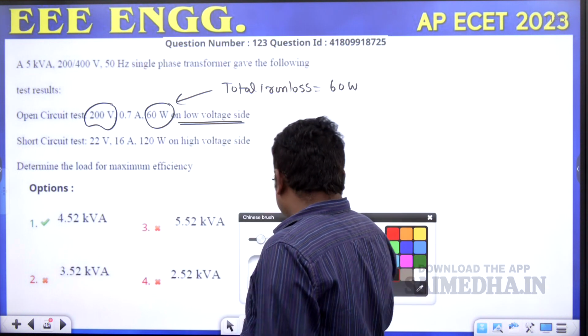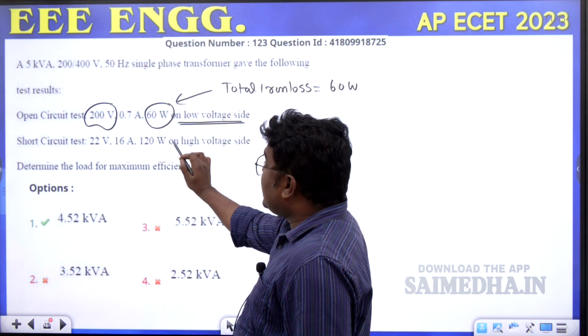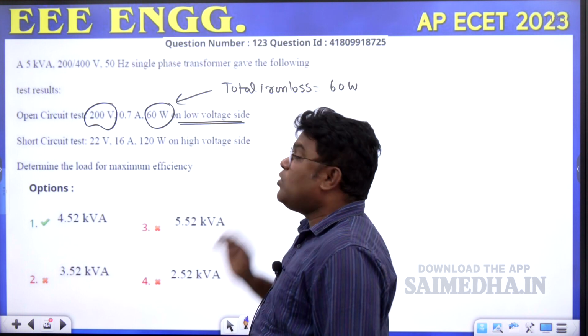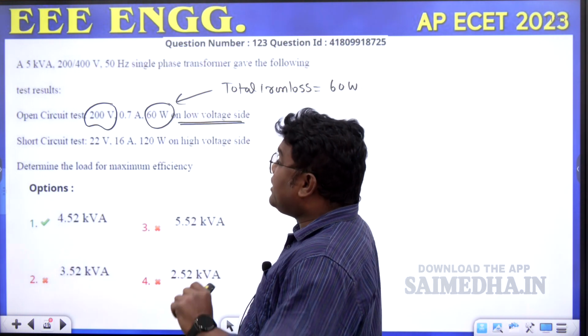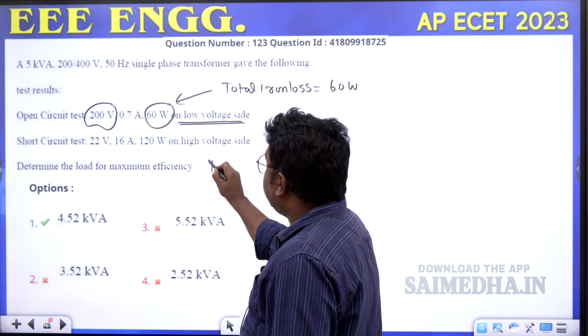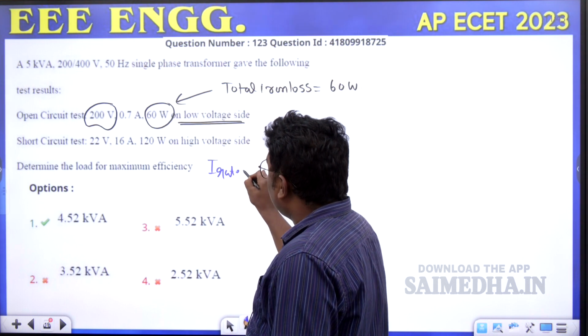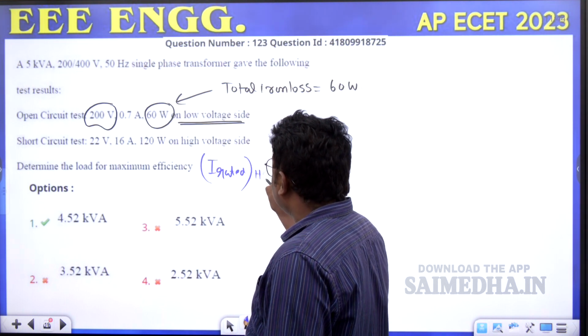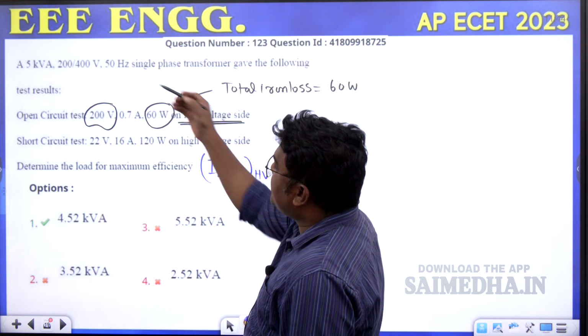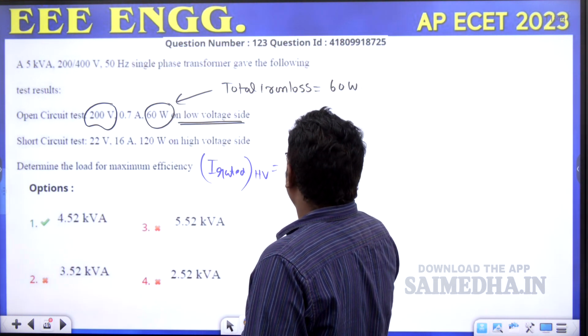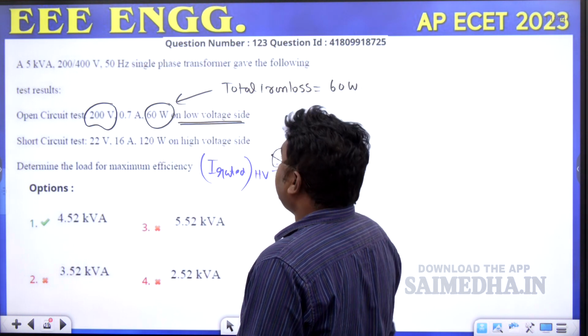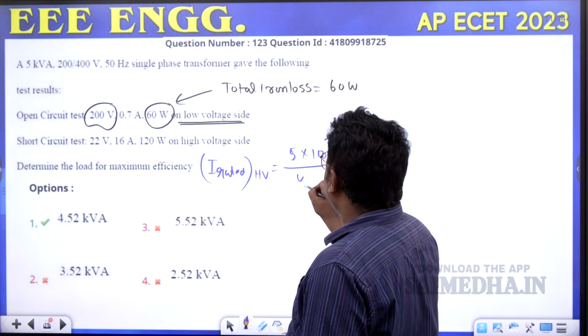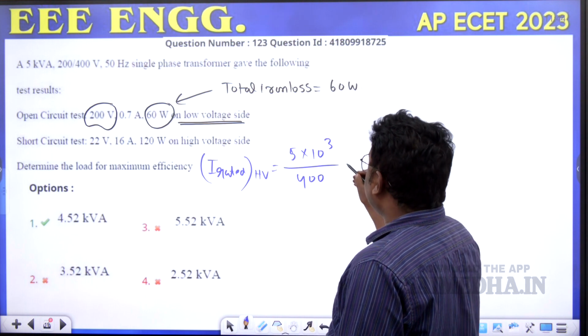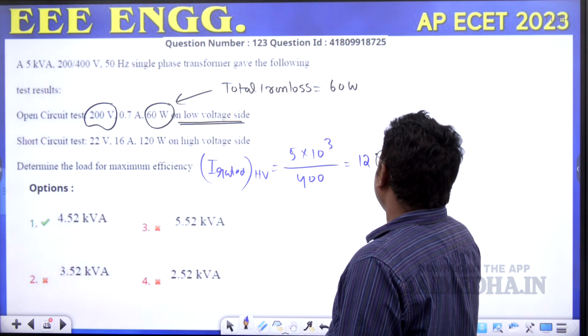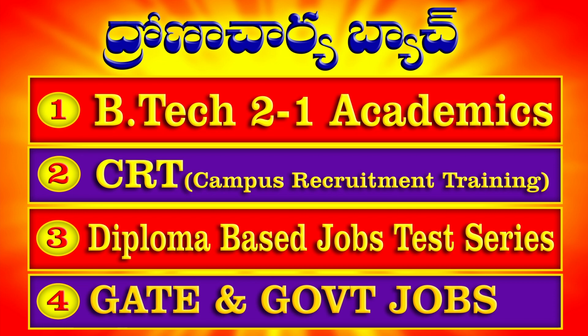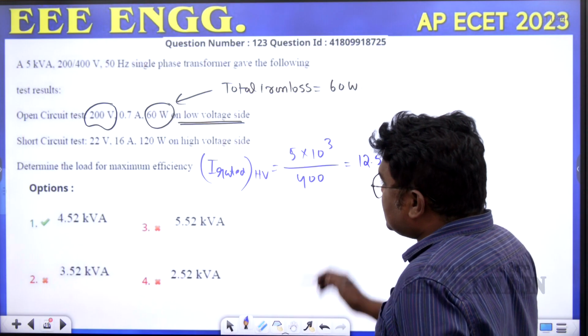Now let us find the rated current. Suppose the short circuit test is conducted on the high voltage side, normally at rated current condition. So I rated, referred to the HV side of the transformer, the high voltage side. So how do we get it? This is 5 into 10 to the power of 3 divided by 400 volts. So 5000 divided by 400 volts, that is 12.5 amps. Now this is the 12.5 amps at this condition.